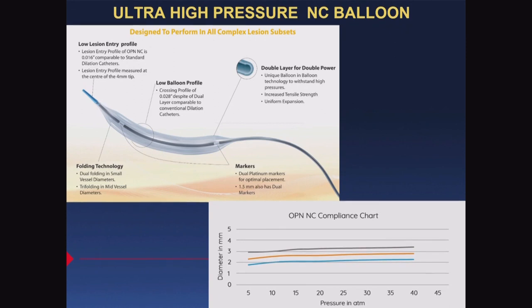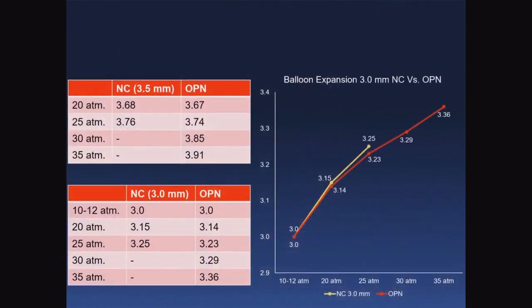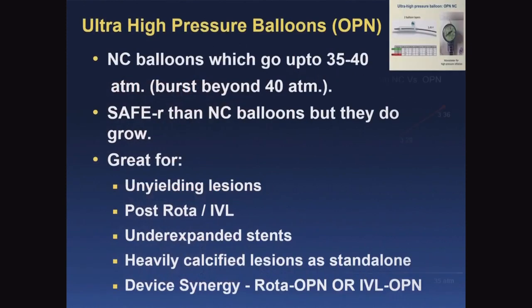The only thing is, look at a 3.5: at 30 atmospheres it's 3.85, at 35 atmospheres it's 3.91, it's grown by 0.06. You must keep track of that in your own mind. It's not as if it doesn't grow. So you need to know the vessel size prior to using ultra high pressure balloons. This is what I was talking about. In comparison, it only grows slightly less than your non-compliant balloon, so keep that factor in mind.